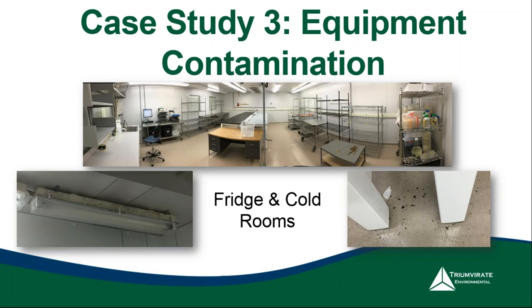As you can see in the photo, the plastic light fixtures obviously have evidence of mold growth in an otherwise pretty clean cold room. We essentially had to power down that cold room, dismantle all the light fixtures, and conduct a thorough cleaning to eliminate that loading in the space.